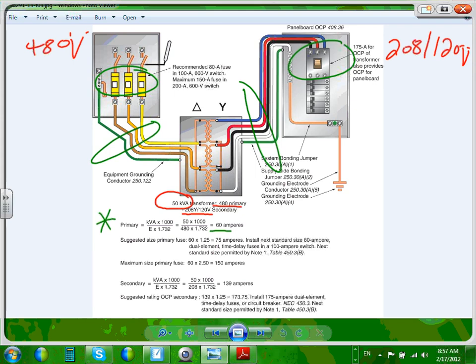So what they did for the fuse, guys, there are two sizes, maximum and suggested. Maximum, if you look at, since we have a primary and secondary protection, we can go as high as 2.5. Can you guys see 2.5 times 60 equals 150? Is 150 a standard fuse? Yep, based on 240. So my primary fuse is going to be 150. It could be lower than that, but my primary fuse is 150.